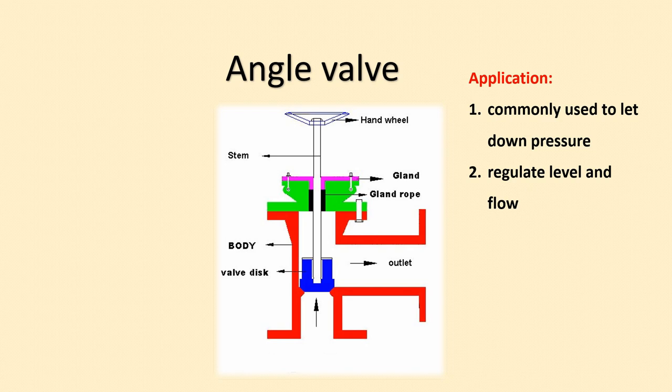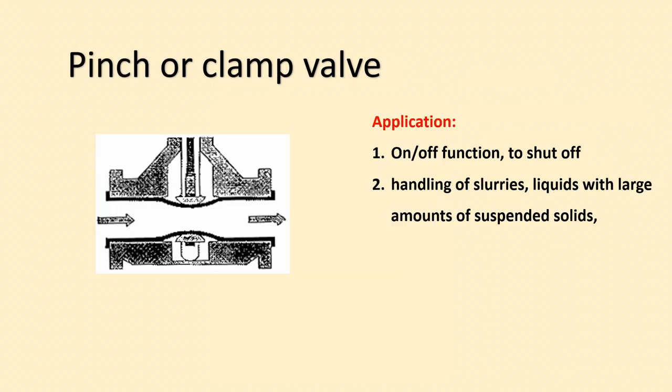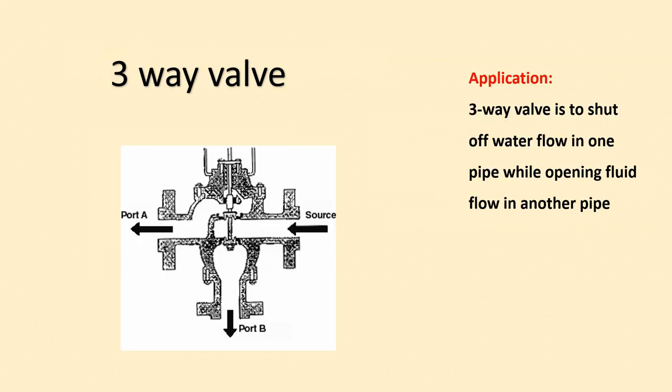Next is the pinch or clamp valve. The body is made of soft material, so it gives the best result in on-off function, mainly for full tight shut-off. The best feature of the pinch or clamp valve is that it can handle slurries, chemicals, and liquors that contain high amounts of suspended solids.